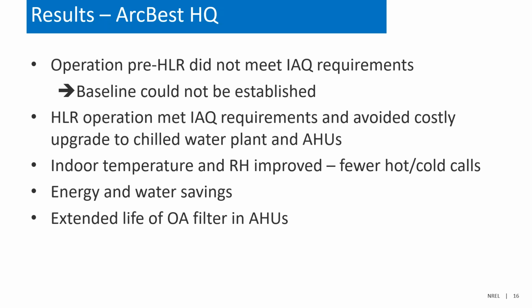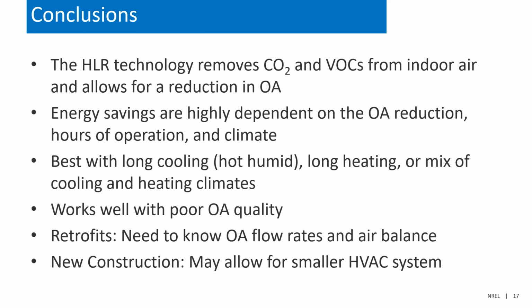And then they were able to show energy and water savings on an annual basis. And also, because they're reducing the amount of outside air intake to the building, they extend the life of the filters in the air handling units. So that's another win, I guess, from the building owner's perspective. So this technology, it works. Well, it removes the CO2 and VOCs and allows you to reduce the outside air.